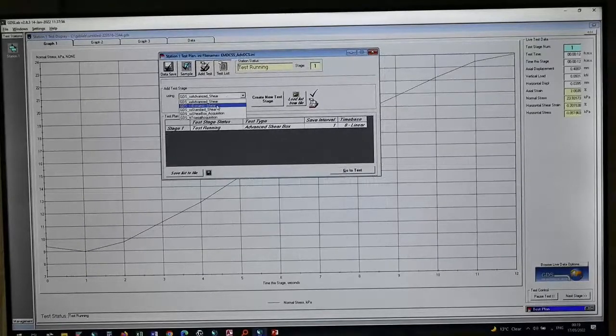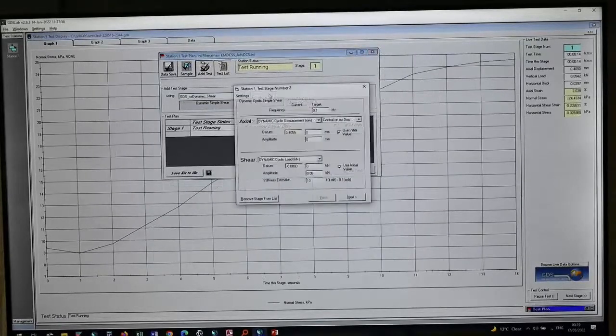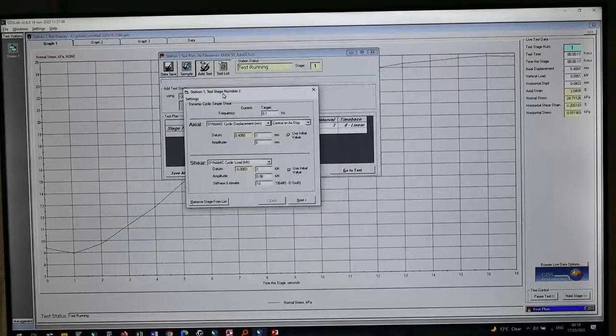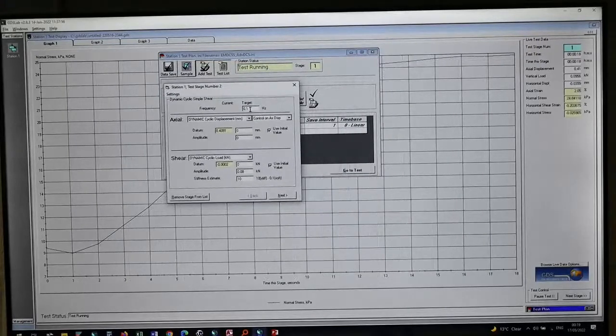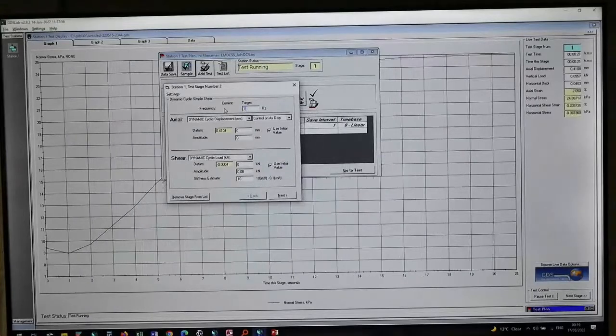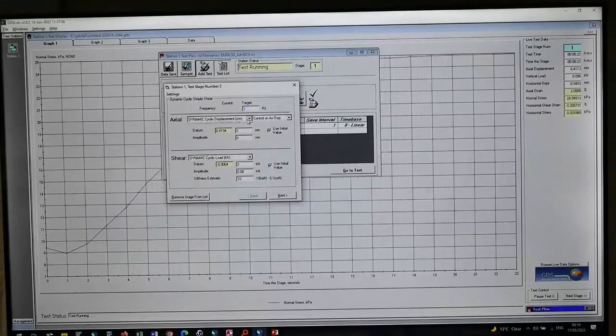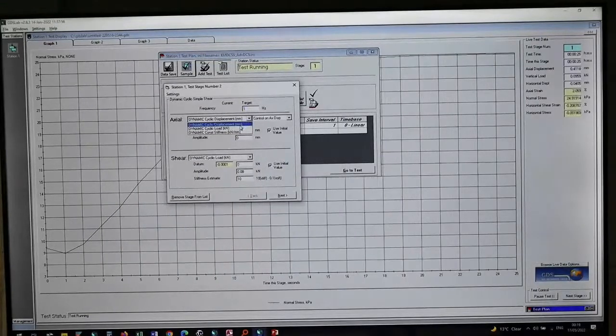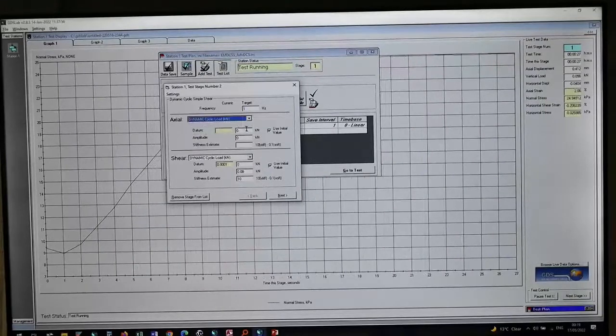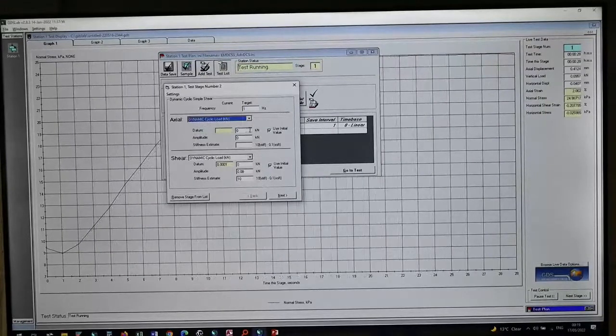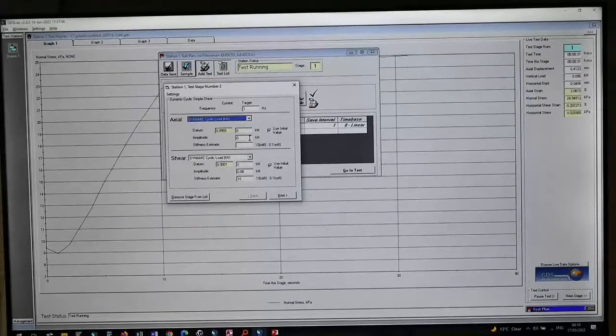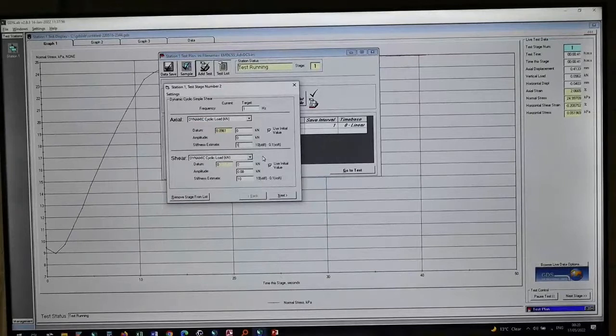I'm going to go to the dynamic shear stage, and I'm going to apply preconditioning on my sample. So in the frequency, I'm going to put 1 Hertz. It's going to be a drained cyclic simple shear test. Load control, so I would keep the current value constant, which is 25 kPa. For the stiffness, I'm going to enter one value because the system is adaptive control, so it's going to adjust its control gains when the stiffness of the sample changes.